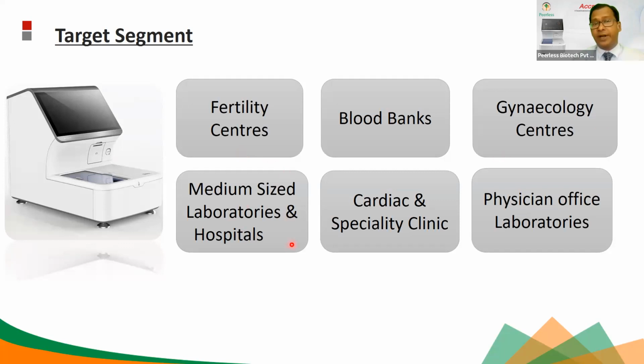Then medium-sized laboratories and hospitals, of course, you can try, because individual labs have a lesser workload, as I said, maximum 15 to 20 tests per day of mixed samples. If someone has too many thyroid tests, they will not go for our machine. They will go for Maglumi. Maglumi offers them better. So why would they go for our machine? Because our machine's CPRT will be much higher than Maglumi's. So they may not be ready. But with mixed tests, a lot of vitamin D, a lot of PCT, some troponin I, a few thyroids, of course, they will love to go for our instrument.